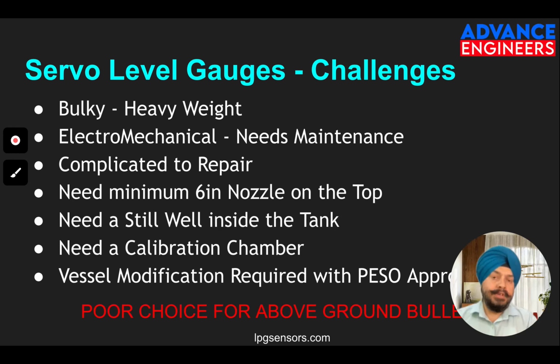So you need to go for a structural analysis. Normally for above ground bullets, the cost you incur in terms of material supply, shutdown, and non-availability of your bullets is going to be very, very high. So it's not recommended to go for a servo gauge on the bullets.